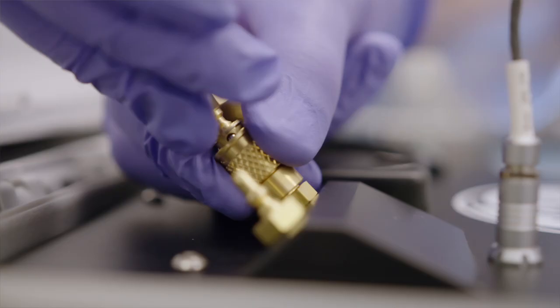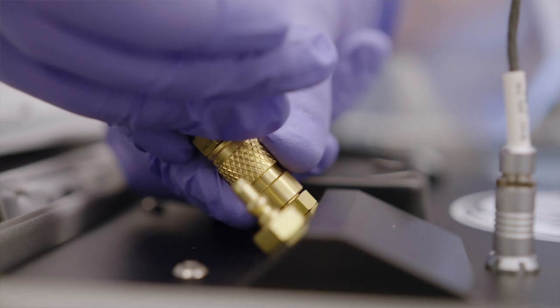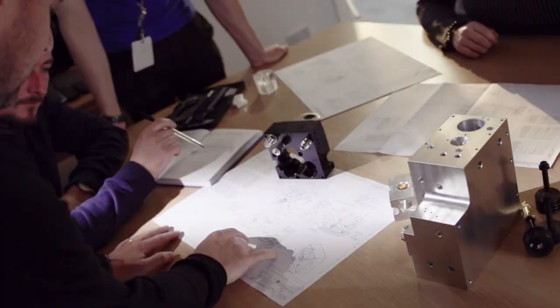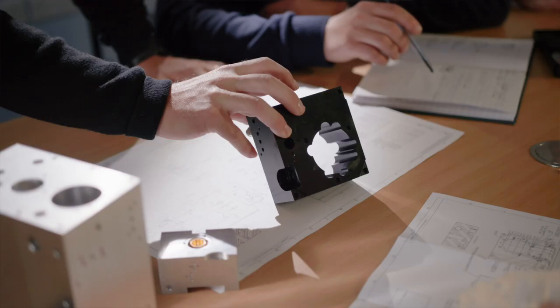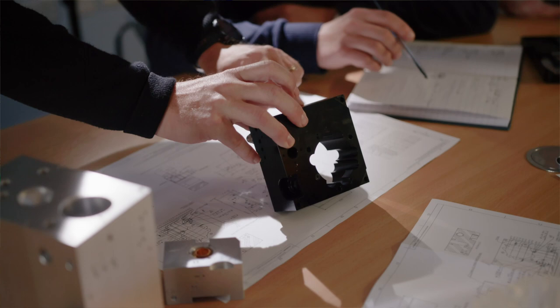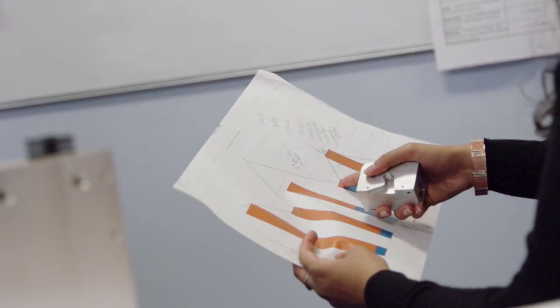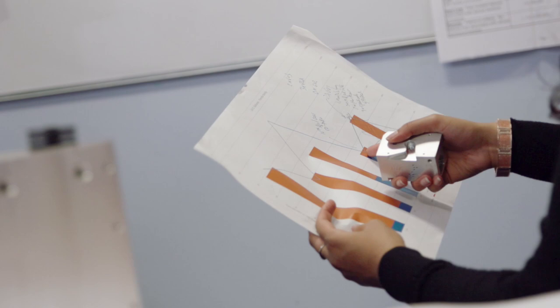And again, that's a really good question because it's not just a case of demonstrating it as a one-off in the laboratory. We have to basically check that there are no additional risks when you start to put this performance in the field at a substation, and also the design. We look at the different aspects of hardware and software. So that particular example, we took the concept of how it's going to operate. We would have reviewed that with a range of the team who have the right skills. So the design engineers, the chief engineer's office would also review as part of our new product process. And then we look for any possible risks and retire those.